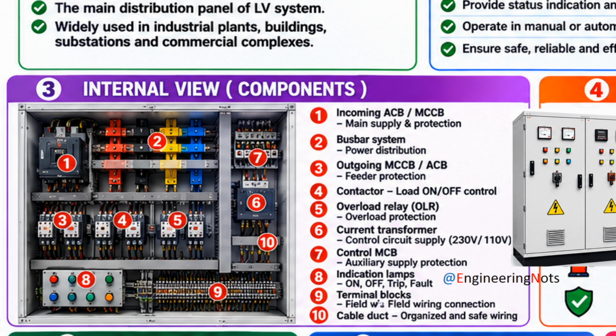Next, we have the copper bus bars. Think of the bus bars as electrical highways. Instead of carrying power through many cables, the bus bars distribute large amounts of current safely and efficiently throughout the panel. Now look at these current transformers, also called CTs. These devices do not carry the load directly. Instead, they measure high current and convert it into a small, standardized current for meters and protection relays. Without current transformers, accurate measurement and reliable protection would not be possible.